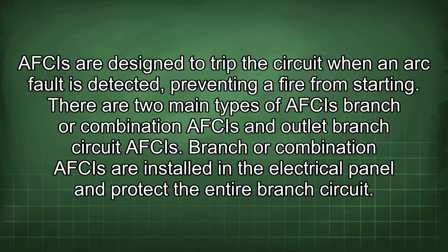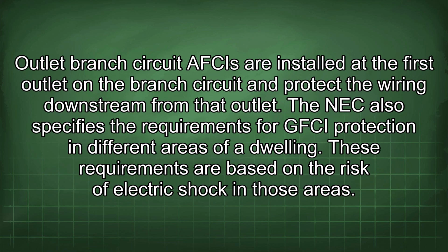There are two main types of AFCIs: branch or combination AFCIs and outlet branch circuit AFCIs. Branch or combination AFCIs are installed in the electrical panel and protect the entire branch circuit. Outlet branch circuit AFCIs are installed at the first outlet in the branch circuit and protect the wiring downstream from that outlet. The NEC also specifies the requirements for GFCI protection in different areas of a dwelling.